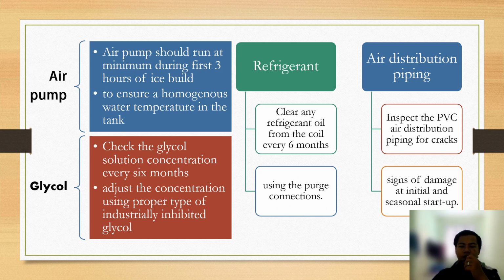This slide shows the cooling medium that needs to be maintained. The first one is the air pump. The air pump should run at minimum during the first 3 hours of ice build to ensure homogeneous water temperature in the tank. After that, for the glycol, check the glycol solution concentration every 6 months. Adjust the concentration using the proper type of industrial inhibited glycol. For the refrigerant, clear any refrigerant oil from the coil every 6 months using the purge connections. For the air distribution piping, inspect the PVC air distribution piping for cracks and any sign of damage at initial and seasonal startup.